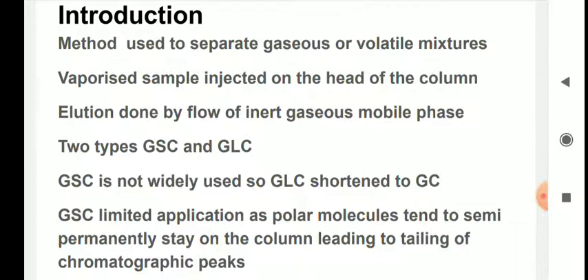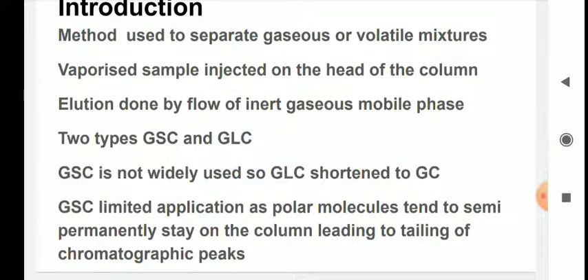GSC is not widely used; GLC is the predominant method in gas chromatography. Nowadays GLC is shortened simply to GC — when you talk of GC it is understood that you are talking of GLC. This is not entirely correct because it sidelines GSC, but the majority of instruments are GLC instruments, so GLC is shortened to GC. GSC applications are limited because polar molecules tend to semi-permanently stay on the column, leading to tailing of the chromatographic peaks.